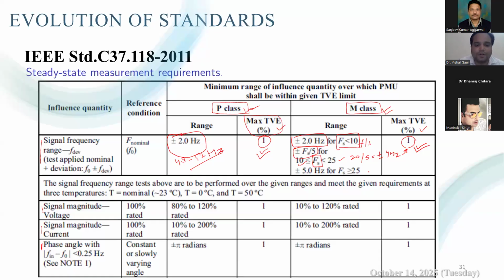For the voltage, you can observe that if the voltage changes or deviates within the range of 80% to 120% of the rated, then the total vector error should remain within the 1% limit. Whereas for the M class, they have given the limit of 1% even if the voltage signal magnitude varies from 10% to 120%.